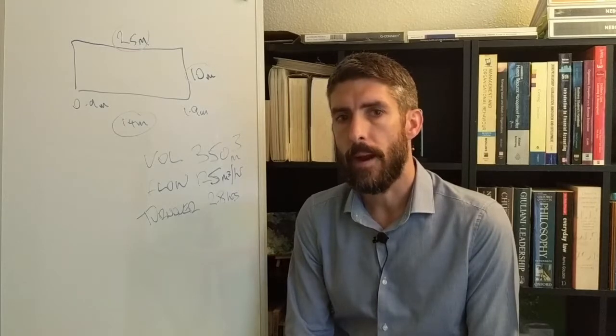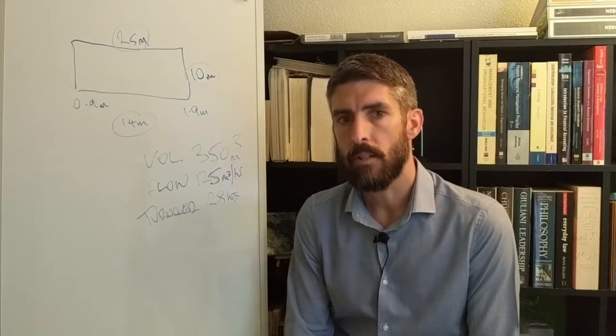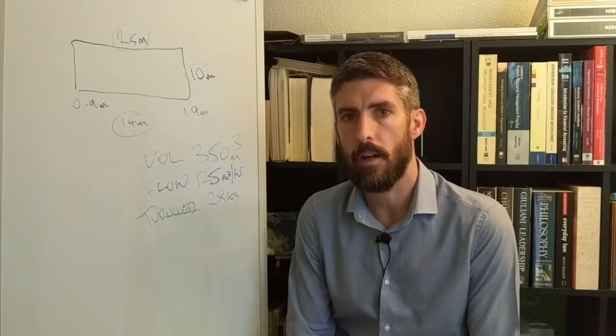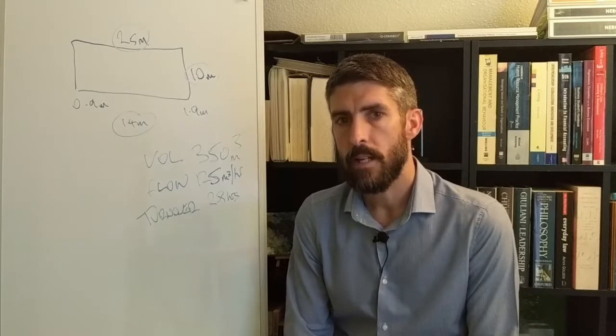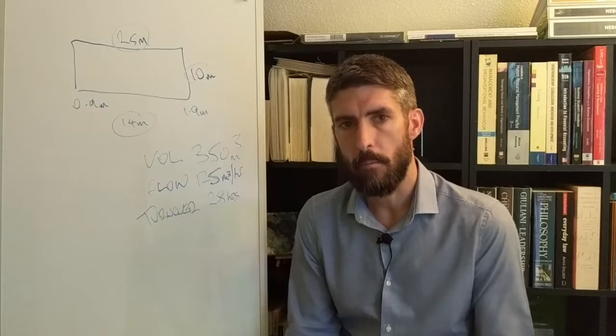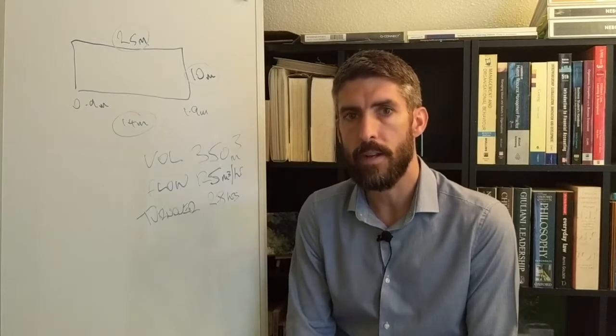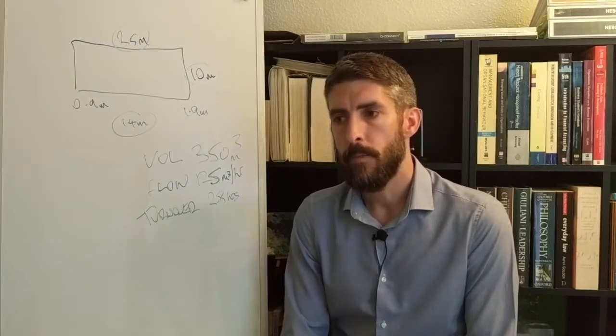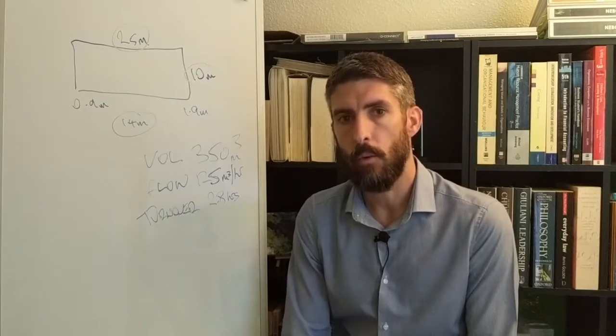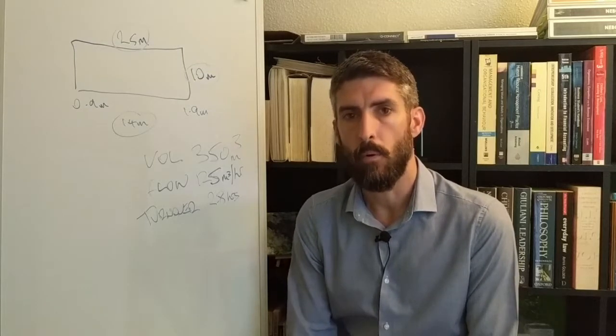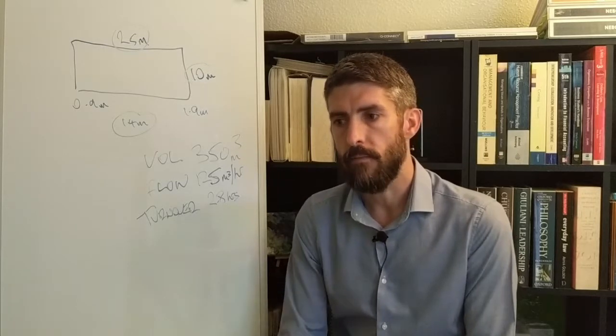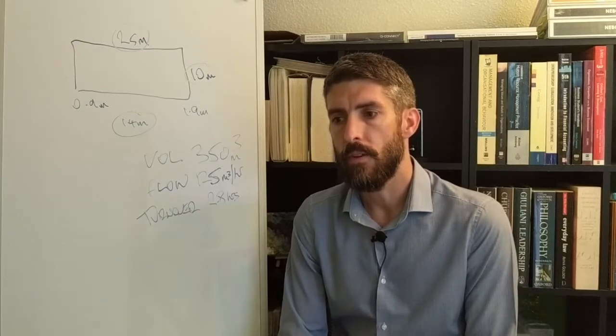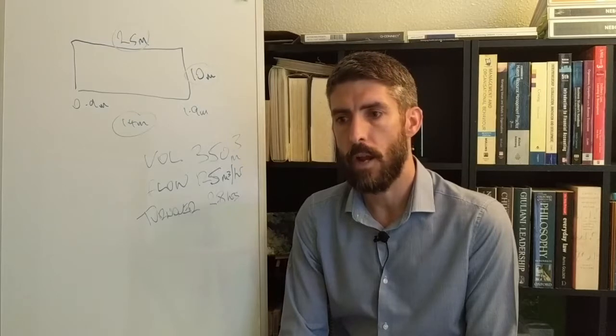So don't feel that you're unique in the fact that if you don't have a flow rate meter you're unique in that respect. I think the problem comes down to the fact that when the pool gets designed and built, and the plant room gets designed and built along with it, a flow rate meter is never specified by the client because the client probably doesn't realize that they're going to need to know what the flow rate is when they start operating that pool. And from the contractor's point of view who's building the pool, you don't actually need a flow rate meter to end up with a perfectly functioning swimming pool. It's the operator that needs this information, and so I think there's a bit of a gap that arises there that results in many pools not actually having a flow rate meter.